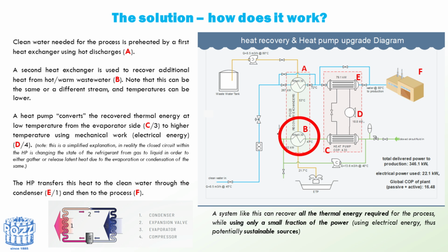Now, the heat pump comes into play. It converts the recovered thermal energy from the evaporator side, at a low temperature, into a higher temperature using electrical energy with very high efficiency, as it's playing with state change and latent heat instead of direct thermal heat transfer. This step allows us to raise the temperature of the energy and make it useful for the process.